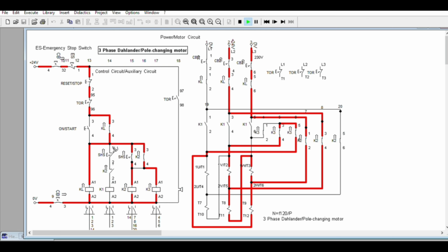Sometimes some will prefer this one because they can see the switch is locked. Because the momentary push button, you cannot identify that it is in the symbol of high speed, especially the lever type handle in some machines. So we have now the line 1, line 2 connecting the two inputs of the star. No current there because same polarity. And this one is forming the double star.